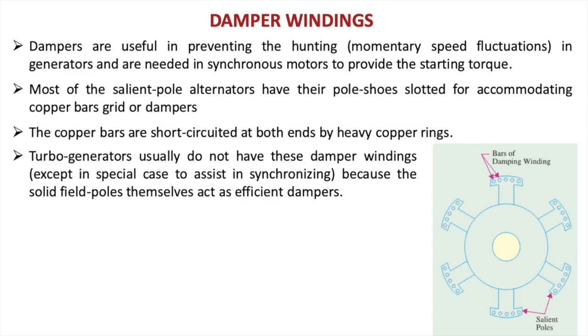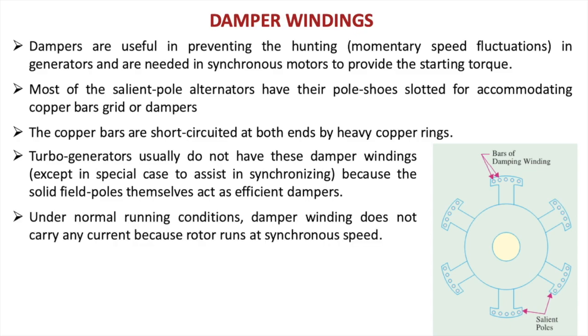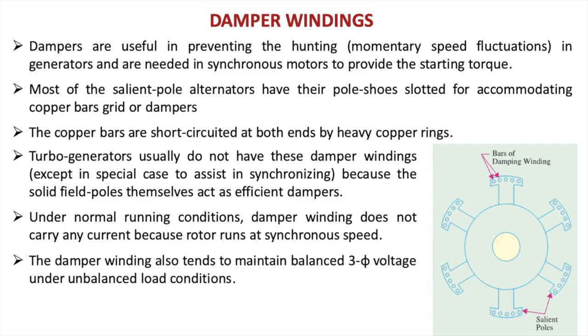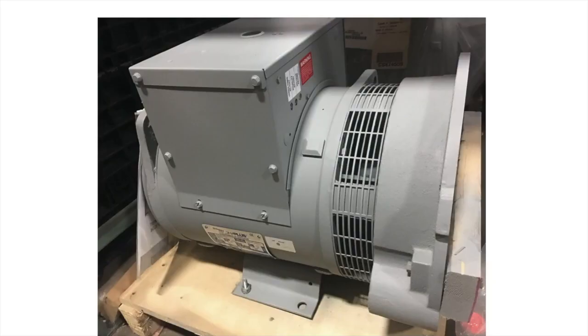Turbo generators usually do not have these damper windings, other than to assist in synchronizing, because the solid field poles themselves act as efficient dampers. Under normal running conditions, the damper winding does not carry any current because the rotor runs at synchronous speed. The damper winding also tends to maintain balanced three-phase voltage under unbalanced load conditions. Here is a small alternator.